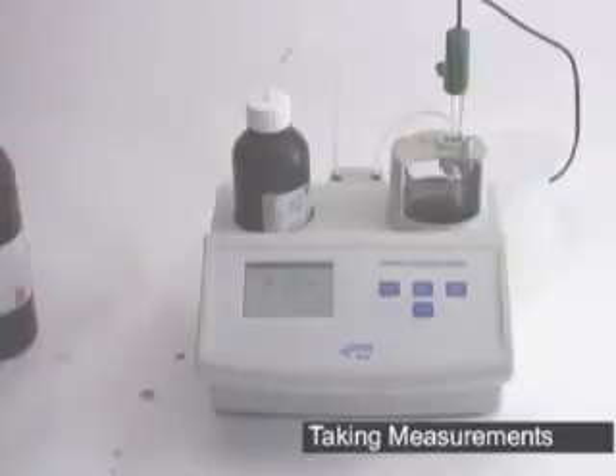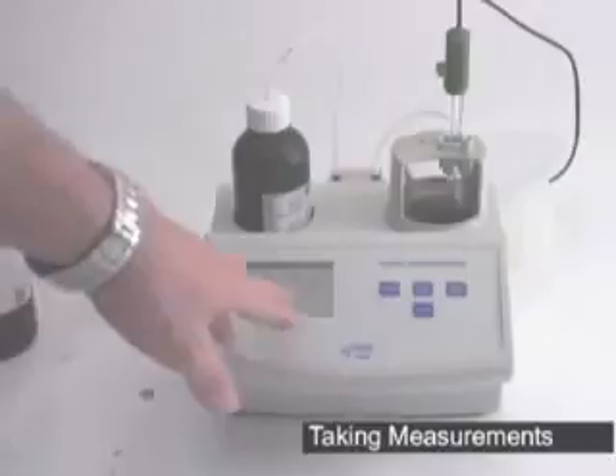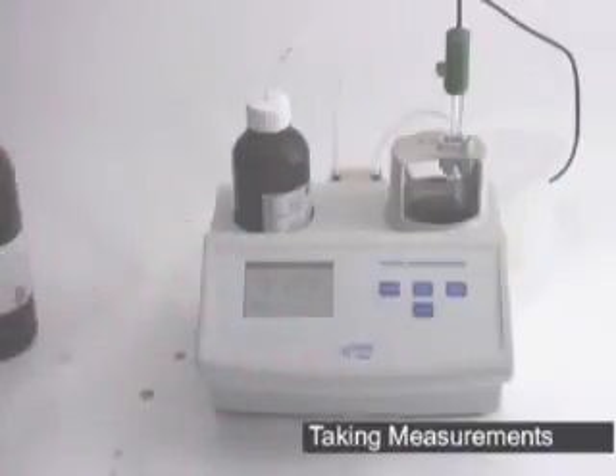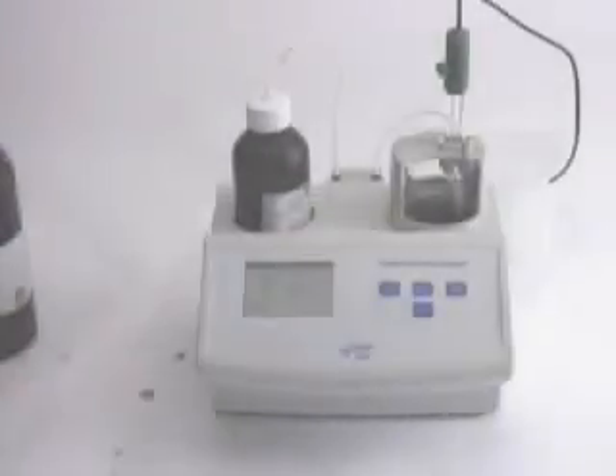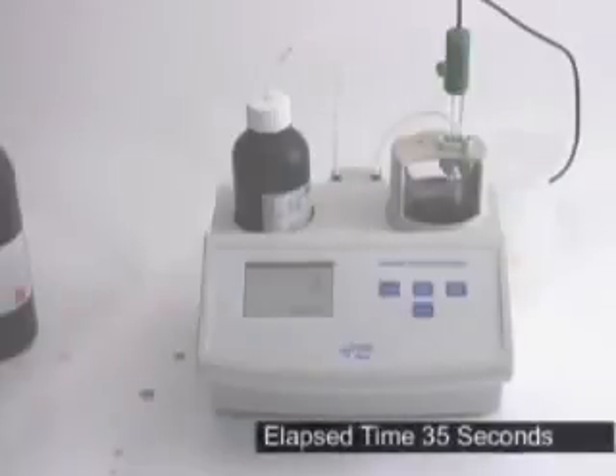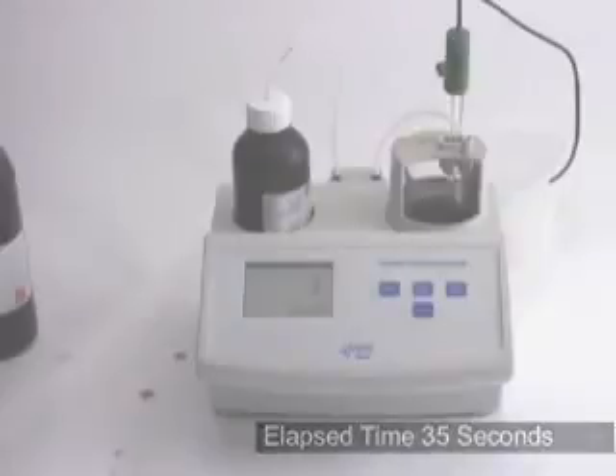Once again, if you do hear your stir bar hitting your probe, just slightly lift your probe, making sure the tip is still submerged past the junction but no longer hitting the stir bar. Once it's finished titration, it'll put the number in parts per million across the screen. Right now we're doing free SO2. And there we go. This one has 3 parts per million of free SO2, as you can see.